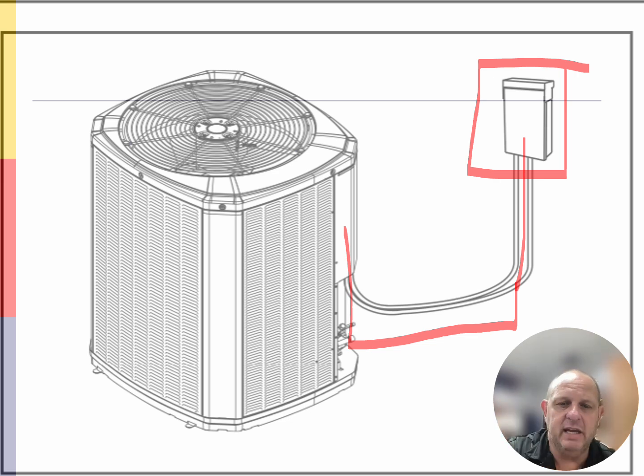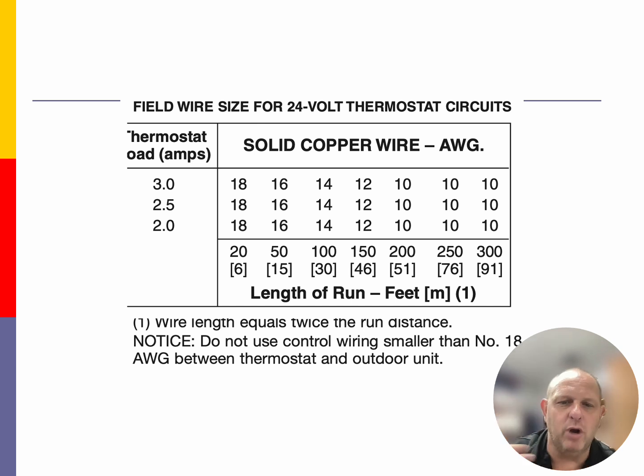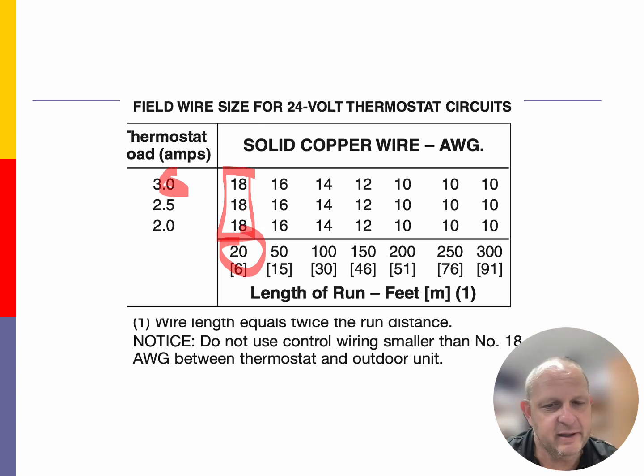As far as our low voltage wiring is concerned, we are going to be running 18 gauge wire. Now, I can tell you for a fact that I've never ever had a problem running 18 gauge wire with the voltage drop on that system. The graph that we are showing you right here is the recommended size control wire for a particular length of run for that wire. You can see that what they're talking about here is 18 gauge wire, good for 3 amps, but they only want you to run that in a total length of 20 feet. That ain't never going to happen in any installation that we're dealing with. I've run 18 gauge wire over 100 feet.